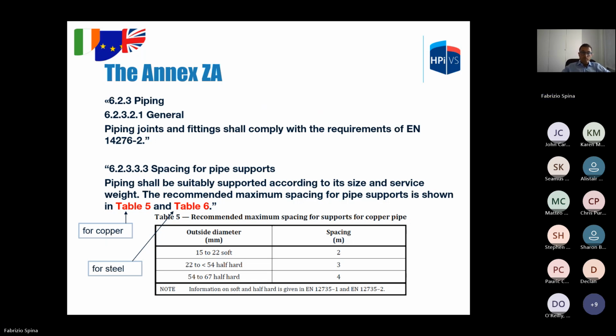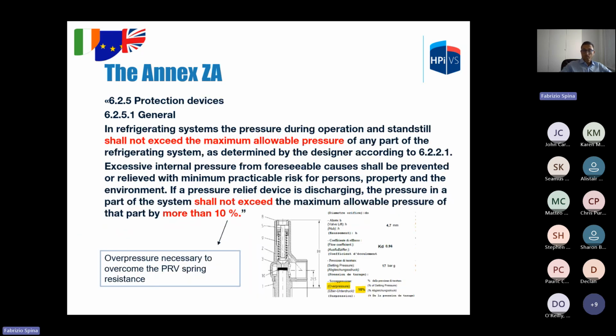6.2.3 Piping. Piping joints and fittings shall comply with the requirements of EN 14276 Part 2. We will check this point later. Spacing for pipe supports. The recommended maximum spacing for supports is specified in Tables 5 and 6 of the standard. Table 5 is for copper, Table 6 is for steel. We have here an example of a snapshot of Table 6, and Table 5. Protection devices. In a refrigeration system, the pressure during operation and at standstill shall not exceed the maximum allowable pressure in any part of the refrigeration system.